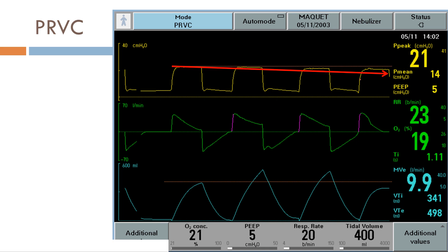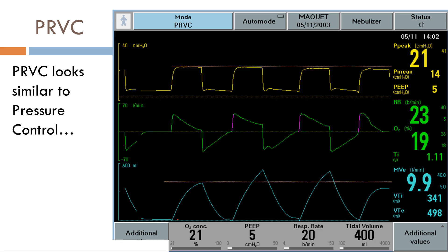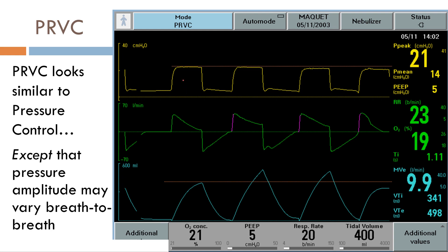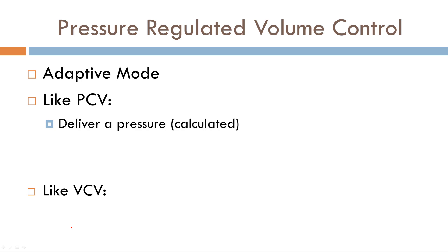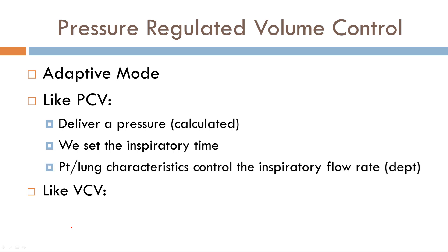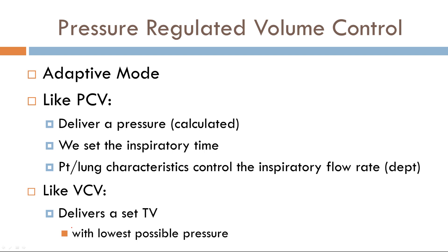Now it's a little odd to have a mode of ventilation where your target variable is not something that you input. PRVC looks pretty similar to pressure control — the waveforms look about the same, and flow is your dependent variable. However, the pressure amplitude may vary from breath to breath. So PRVC is an adaptive mode, and the pressure will change with time as compliance changes. It uses features from both pressure assist control ventilation and volume assist control ventilation. Like pressure control, it delivers a pressure, but this pressure is calculated; we set the inspiratory time as the cycle variable, and flow is completely dependent on the patient's demands or lung characteristics. Like volume control, you deliver a set tidal volume with the lowest possible pressure.